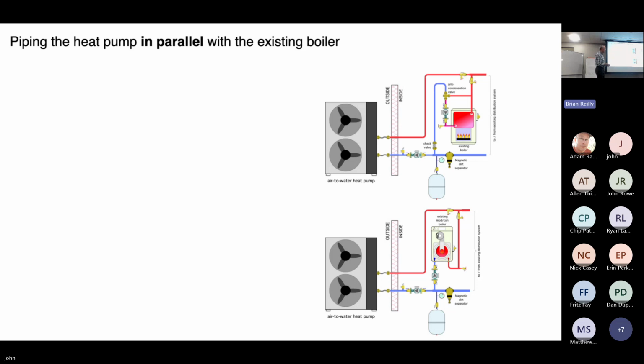This boiler loves that. But this one is made out of a high grade of stainless steel heat exchanger. This is cast iron. Okay. This is vented through very high grade stainless or other polypropylene materials that can handle the condensate. This is vented through galvanized steel pipe, and it's going to corrode. So if you're retrofitting or if you're installing a conventional, like an oil-fired cast iron boiler, you need an anti-condensation valve to protect it.